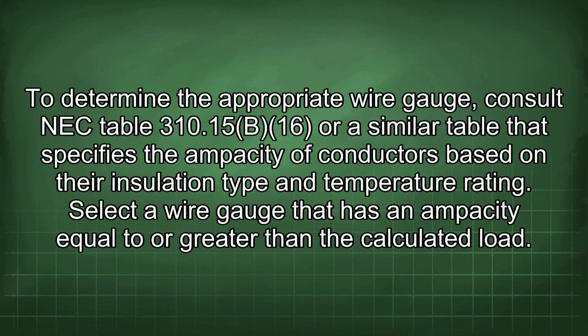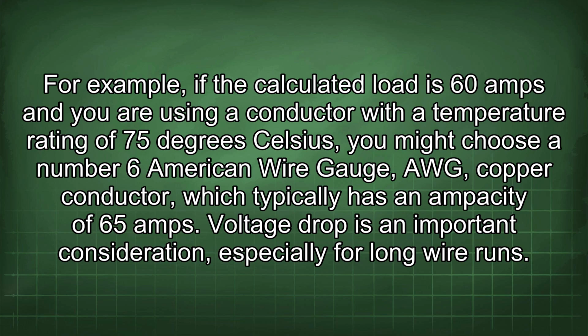To determine the appropriate wire gauge, consult NEC Table 310.15(B)(16) or a similar table that specifies the ampacity of conductors based on their insulation type and temperature rating. Select a wire gauge that has an ampacity equal to or greater than the calculated load. For example, if the calculated load is 60 amps and you are using a conductor with a temperature rating of 75 degrees Celsius, you might choose a number 6 American Wire Gauge, AWG, copper conductor, which typically has an ampacity of 65 amps.